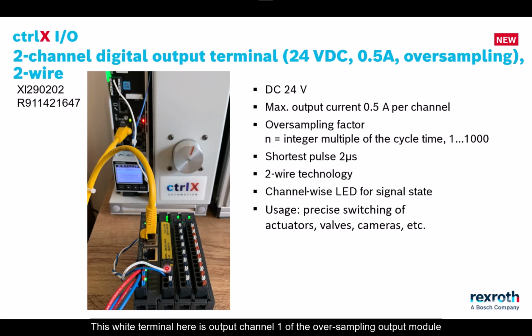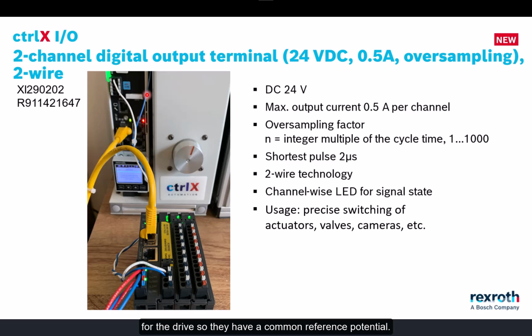This white terminal here is output channel 1 of the Oversampling Output Module, and it is wired to the first input on the ctrlX drive, which by default is configured as a probe input. The probe inputs are used for high resolution capturing of position or time based on the rising or falling edge of an input. And then the blue terminals are the reference or common for 24 volts. In this case, the I/O coupler and the drive are on different 24 volt power supplies. So I have a wire connecting the 0 volts of the I/O to 0 volts for the drive so that they have a common reference potential.